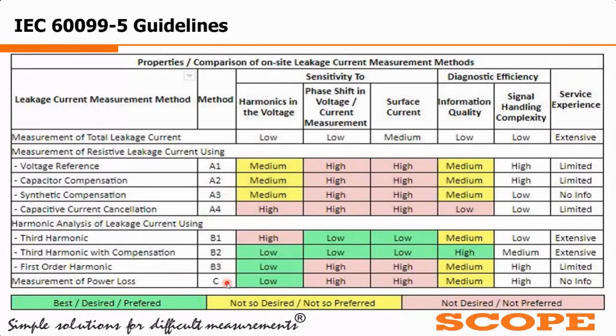These are the total 8 measurements, and they have compared them from various angles: the sensitivity and diagnostic efficiency. In the sensitivity, they have considered the harmonics in the voltage, phase shifting, how much is happening in the voltage or current measurement, and how much is the effect of the surface current on the LA. They also considered the measurement information, how much qualitative information I am getting during the measurement, and how complex it is to do the signal handling, because whatever we measure, we need to handle the signal, and finally the service experience. So they have rated these as medium, high, and low.